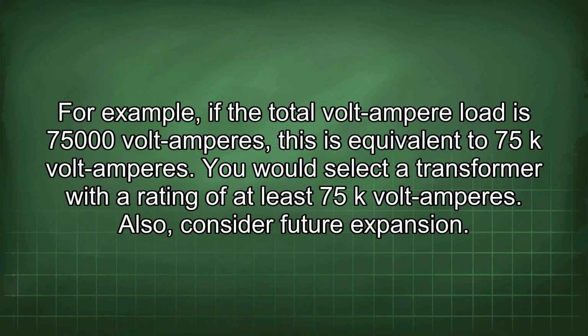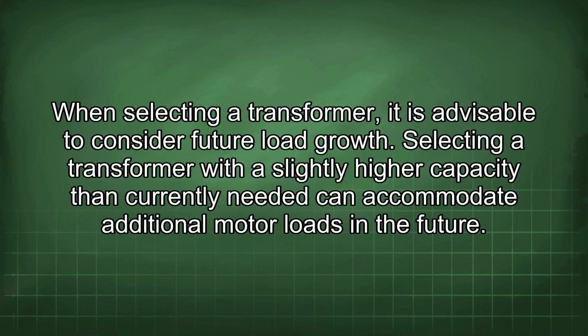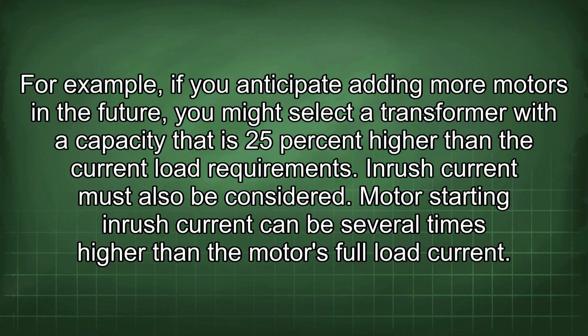Also, consider future expansion. When selecting a transformer, it is advisable to consider future load growth. Selecting a transformer with a slightly higher capacity than currently needed can accommodate additional motor loads in the future. For example, if you anticipate adding more motors in the future, you might select a transformer with a capacity that is 25% higher than the current load requirement.